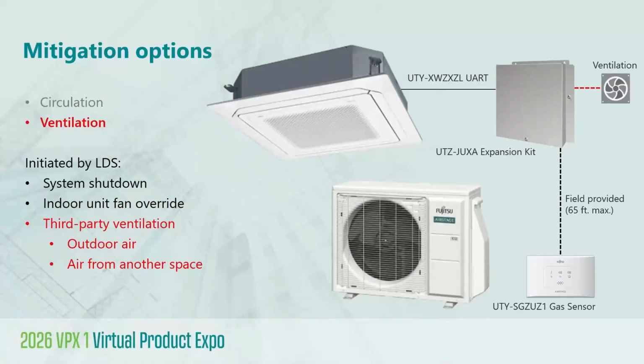Now, by comparison, the ventilation mitigation option operates quite differently, even though it is initiated by the same LDS, the gas sensor, again, whether factory installed or the wall-mounted option that you see there. Now, in this configuration, a third-party ventilation fan that you see in the upper right is connected through an external output from the expansion kit. So the expansion kit doesn't power the fan itself. Rather, it's a 12-volt output that operates a DC relay that completes either a line voltage or low voltage control circuit required to operate the fan.